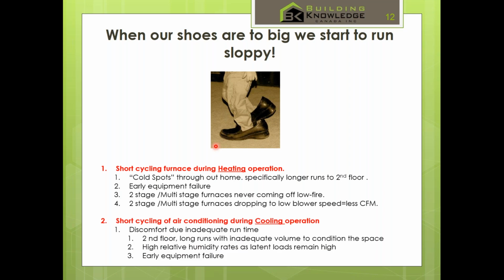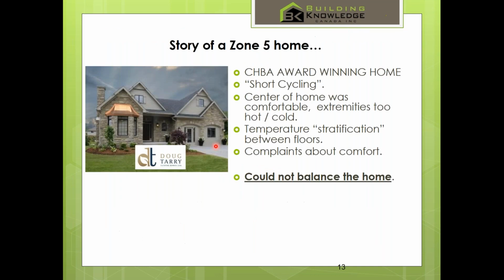Air conditioning, the short cycling during cooling operation does a couple more things. Not only does it not get the conditioned air to the rooms, but because an air conditioner is meant to both cool the air and to dehumidify, the dehumidification mode, or the latent recovery mode in an air conditioner, is typically associated with a longer cycle. And when an air conditioner short cycles, it ends up blasting the house with cold air, but never running long enough to dehumidify it, and you start to get this cold, damp, cave feeling in your home. And one of the first signs is basements that are incredibly humid, and you start to get that wonderful smell where the rest of your house now smells like your old basement in your old house did. All happening in new energy efficient homes.